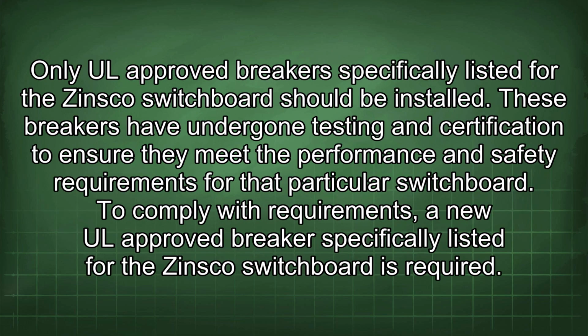Only UL-approved breakers specifically listed for the Zinsco switchboard should be installed. These breakers have undergone testing and certification to ensure they meet the performance and safety requirements for that particular switchboard. To comply with requirements, a new UL-approved breaker specifically listed for the Zinsco switchboard is required.